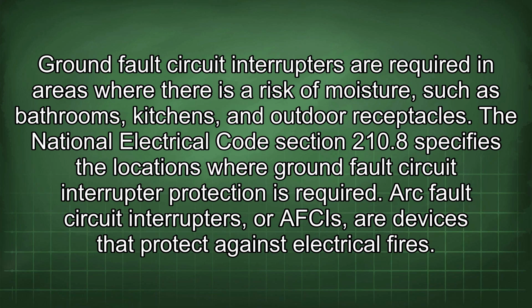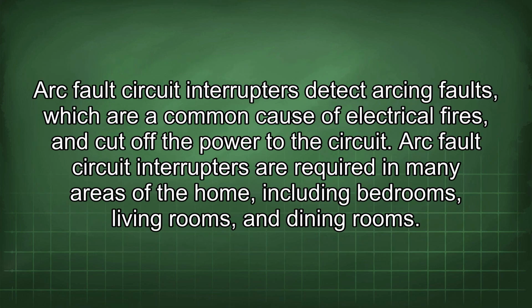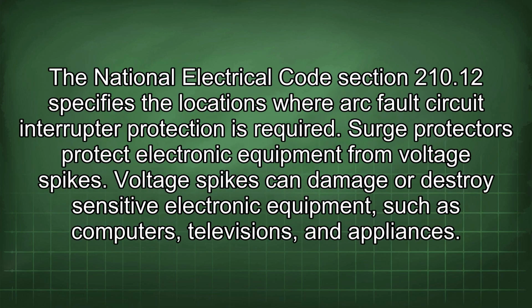Ground fault circuit interrupters are required in areas where there is a risk of moisture, such as bathrooms, kitchens, and outdoor receptacles. The National Electrical Code Section 210.8 specifies the locations where ground fault circuit interrupter protection is required. Arc fault circuit interrupters, or AFCIs, are devices that protect against electrical fires. Arc fault circuit interrupters detect arcing faults, which are a common cause of electrical fires, and cut off the power to the circuit. Arc fault circuit interrupters are required in many areas of the home, including bedrooms, living rooms, and dining rooms. The National Electrical Code Section 210.12 specifies the locations where arc fault circuit interrupter protection is required.